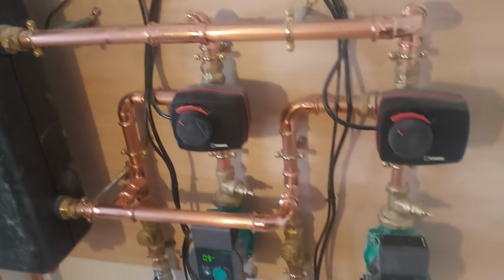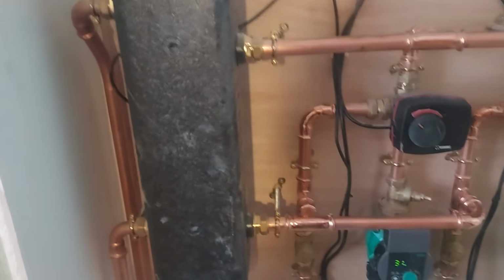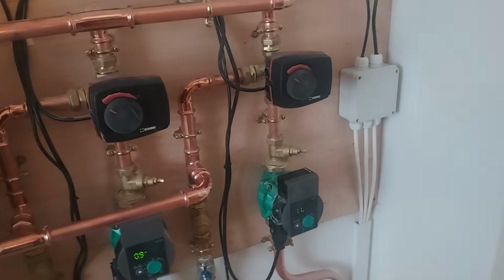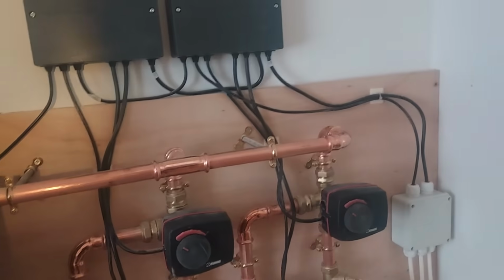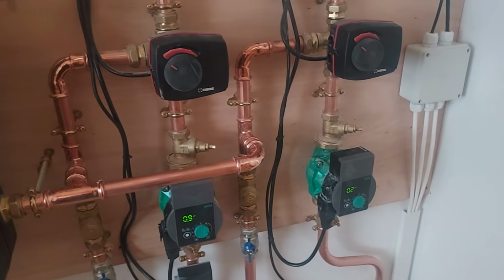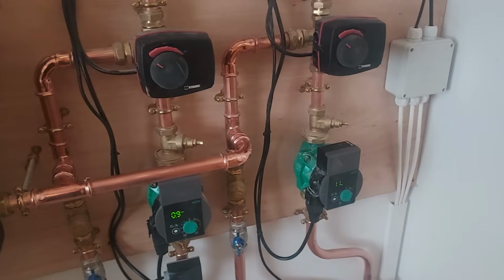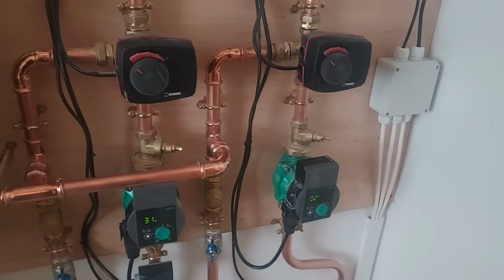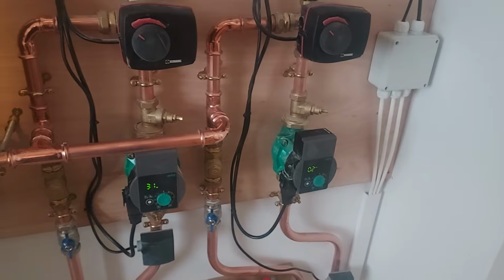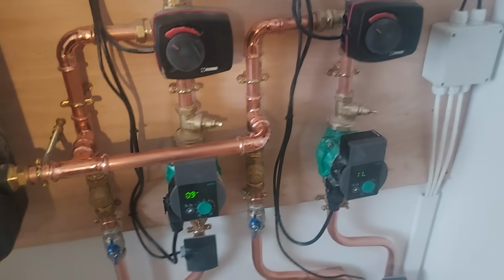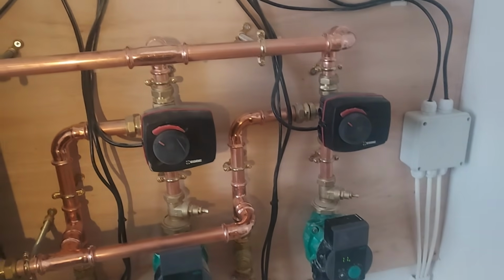So another little system we've done. This is a Viessmann 222 with two mixed circuits, no unmixed circuits. It's radiators upstairs, underfloor downstairs. But doing the calculations, the radiators upstairs would be running over output if they were an unmixed circuit running at the same temperature as the underfloor, and especially on night setback. So we're unable to use an unmixed circuit.